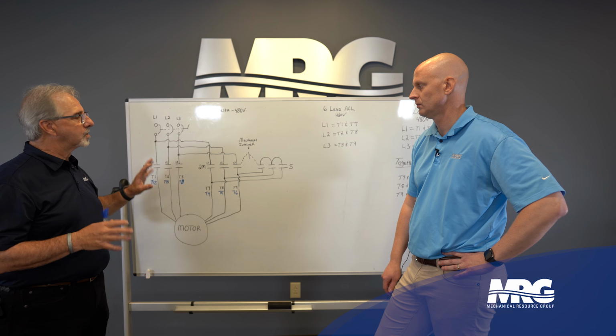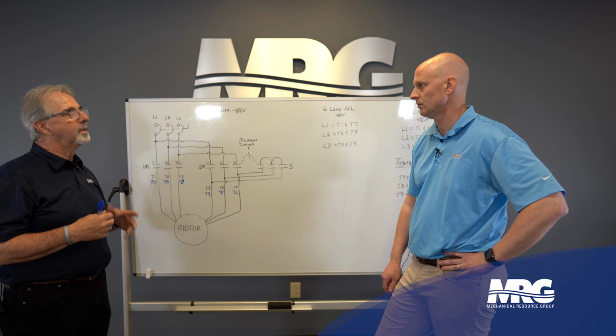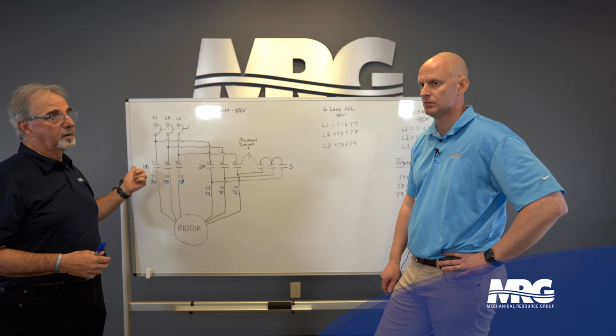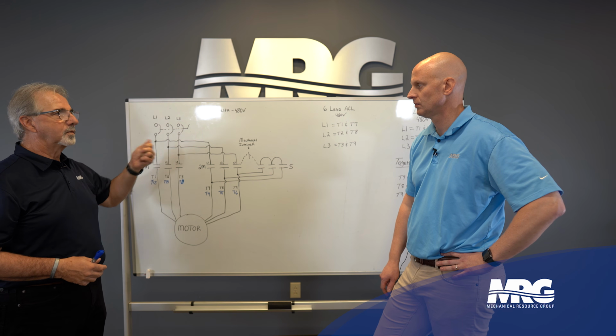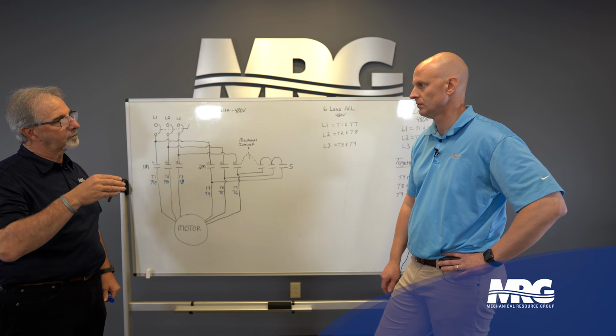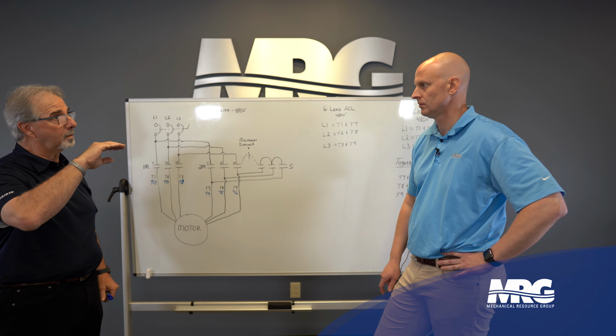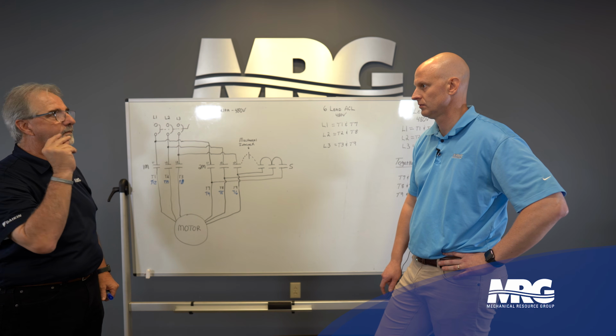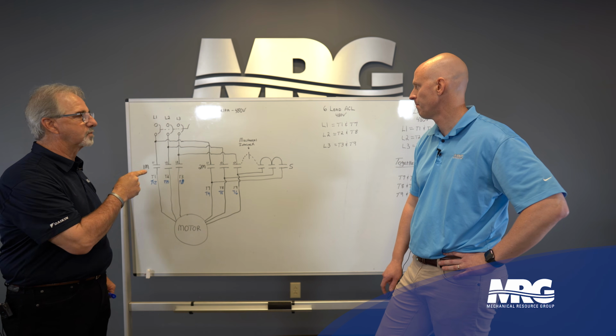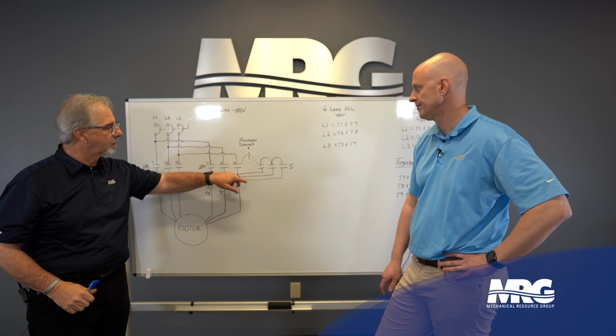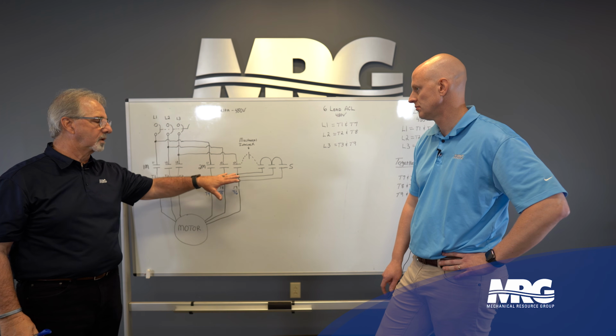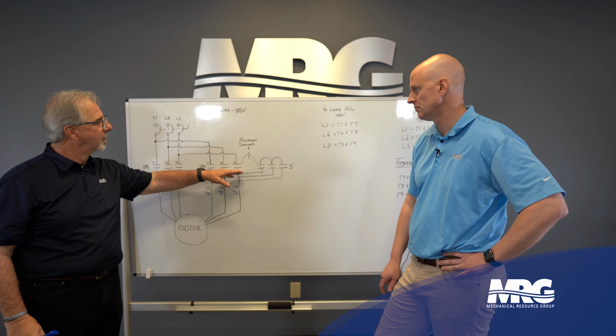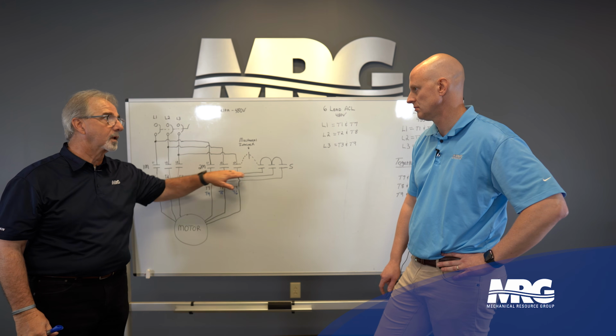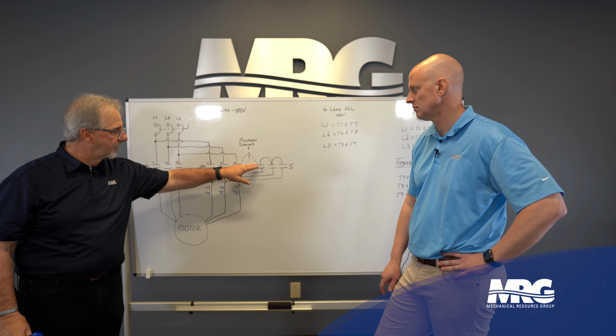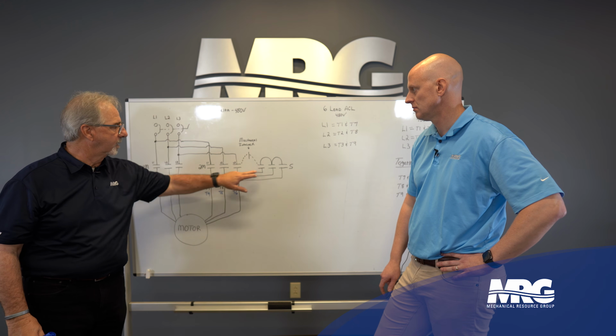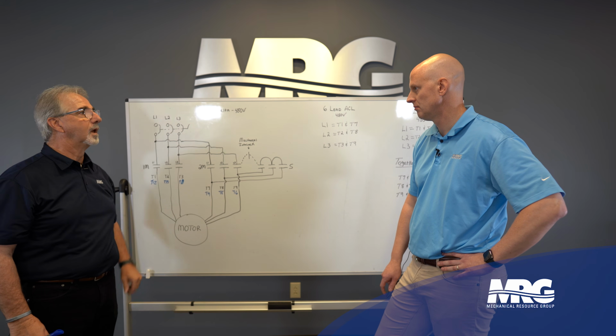Generally, the way that I have our guys set it up, put your amp probe on either line 1, 2, or 3 and measure it. When you start it, the current is going to come up. When you see the current start to fall off, that's when you want to make that transition. That's when we set the timer. But it's very critical, and unless the mechanical interlock is broken, there's no risk of shorting the starter out, because this won't allow this to come in unless that is fully disengaged. And then it comes in.